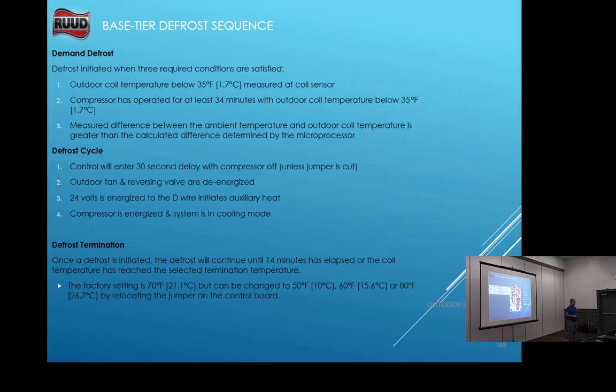Before that unit can go into defrost, it has to have an outdoor temperature below 35 degrees, and it has to stay below 35 degrees for 34 minutes. Then there's a temperature difference between the outdoor and the indoor, with an algorithm, before it sends that unit into defrost. We'll show you in a little bit how we can put it into demand defrost so we can check that it's working properly and will go into defrost, okay?